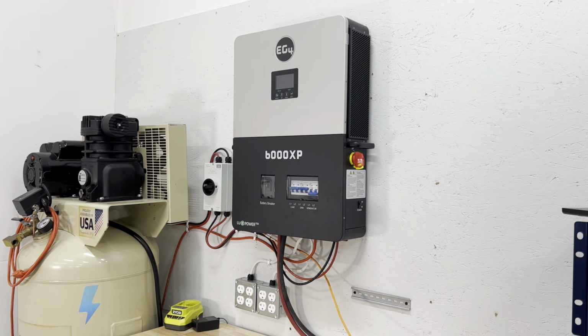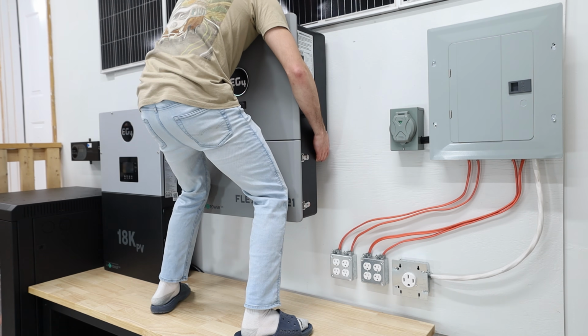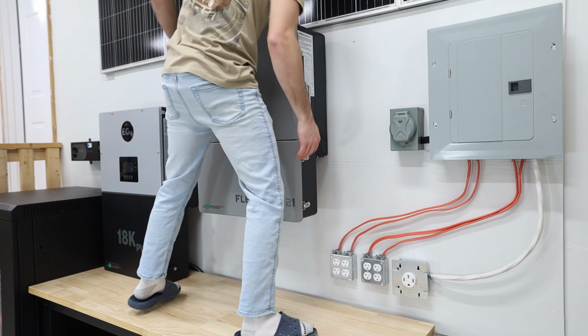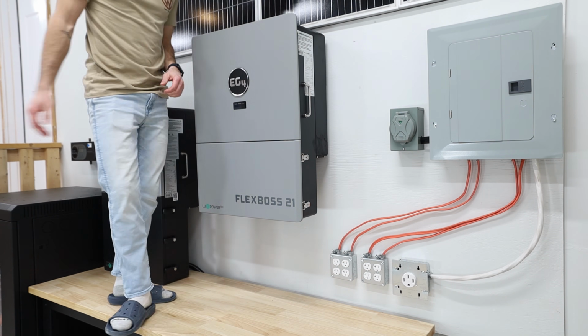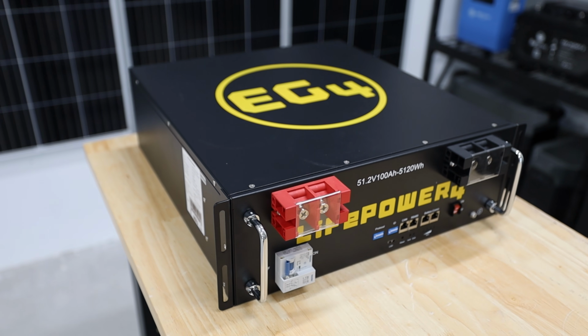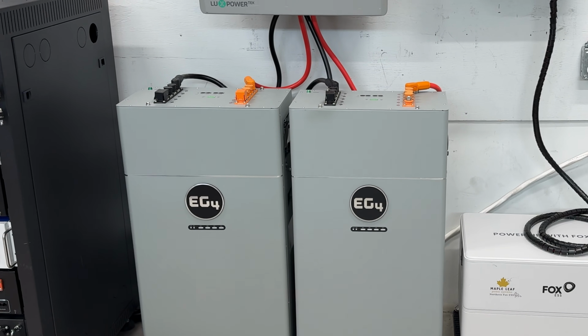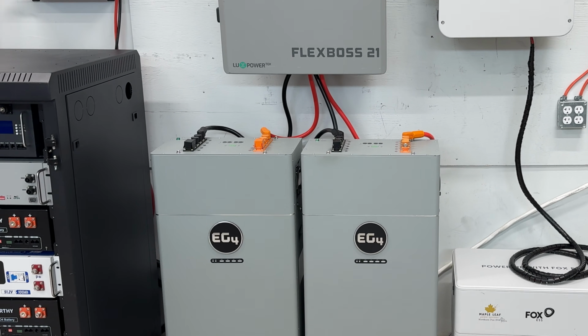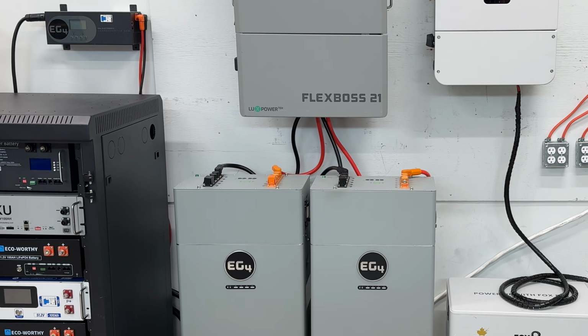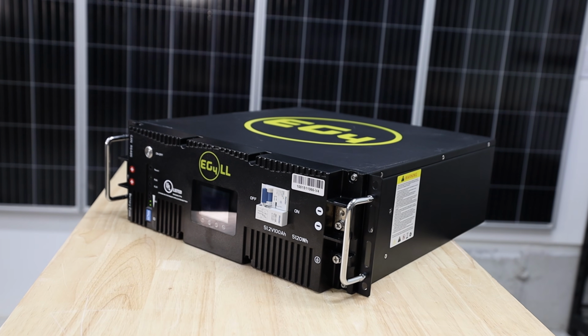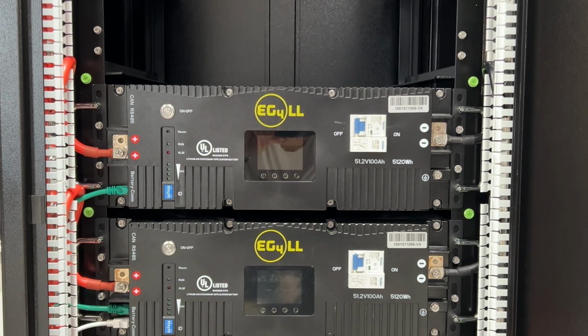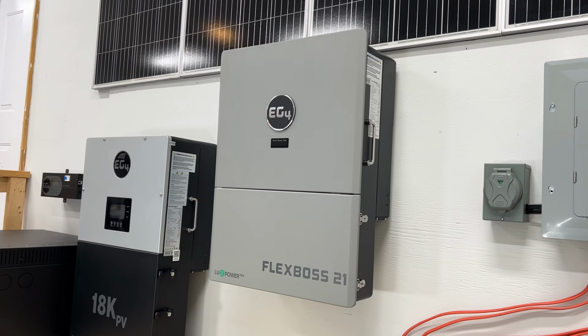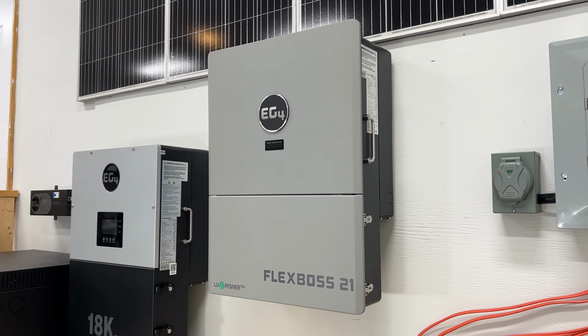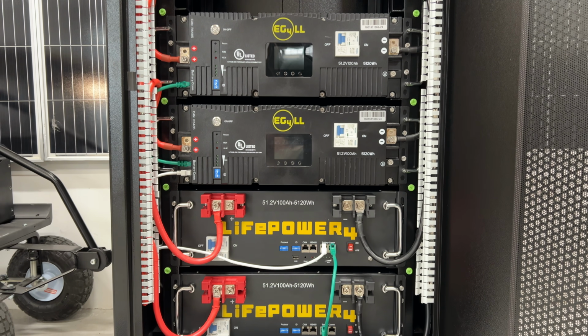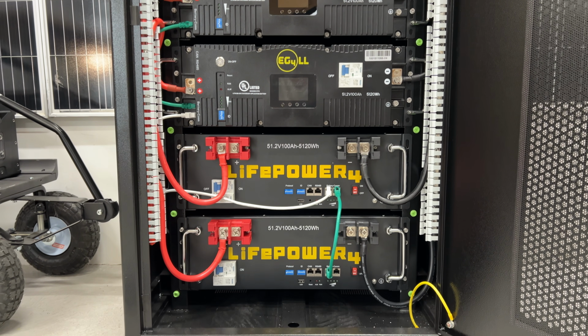If you have a bigger system, say a FlexBOSS, it requires a certain amperage to give you the full output. So if you only had one server rack battery attached to a FlexBOSS, you won't get your 12,000 watts out of it until you have a battery with high enough output. But once you go past that, everything stays at 12,000 watts, you're good to go. For example, one server rack is about 100 amps, so two server racks is 200 amps, and once you hit that 250 amp marker on the FlexBOSS, you're done. Every battery you add just adds capacity, and your output remains the same at 12,000 watts.